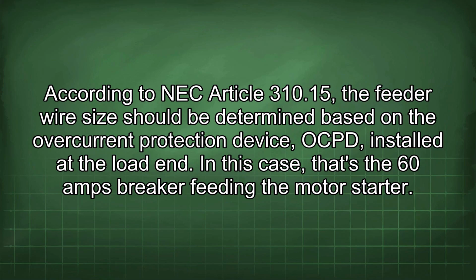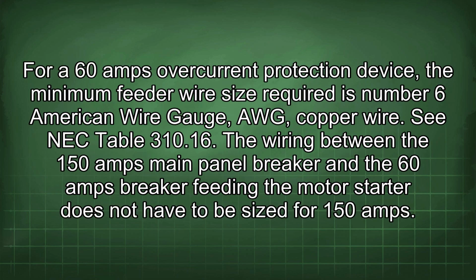According to NEC Article 310.15, the feeder wire size should be determined based on the overcurrent protection device (OCPD) installed at the load end. In this case, that's the 60 amp breaker feeding the motor starter. For a 60 amp overcurrent protection device, the minimum feeder wire size required is number 6 American Wire Gauge (AWG) copper wire. See NEC Table 310.16.